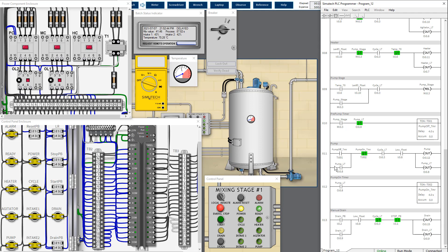When the pump output is energized it triggers a virtual switch to open and de-energizes timer-on relay one. Because the pump is energized, it also triggers another virtual switch to close so current flows to energize timer-on relay two. After four seconds, timer-on relay two turns on, de-energizes the pump, and allows the normally closed contact to remain closed so current can flow again to restart the pump cycle. In summary: the system waits four seconds, then pumps for four seconds, and this process repeats.